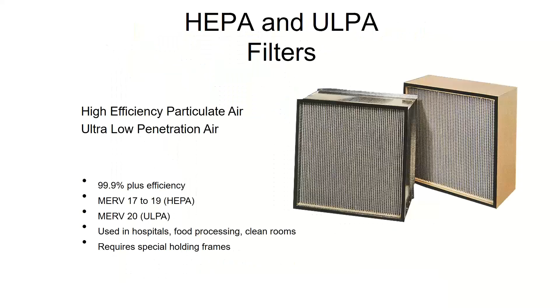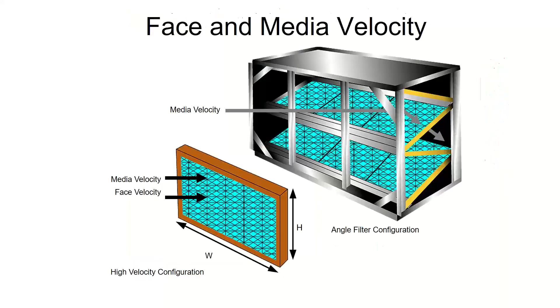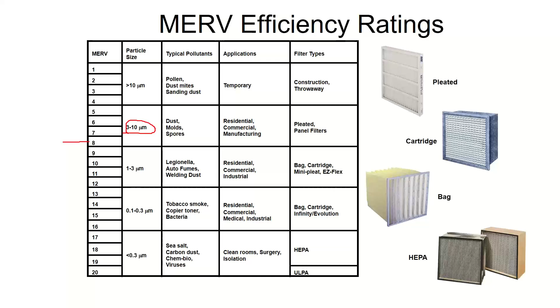Greg asks, are the Merv values additive? If you have a Merv 8 and another Merv 8, does that equal Merv 16? It does not, that's actually a good question, no one's ever literally asked me that before. The Merv rating is a function of how small of things I can catch, not how many times I've tried to catch them. So if I have a Merv 8 filter, it can only catch stuff down to 3 to 10 microns, meaning some stuff smaller than 3 microns will fit through the hole, so everything from there down fits through.